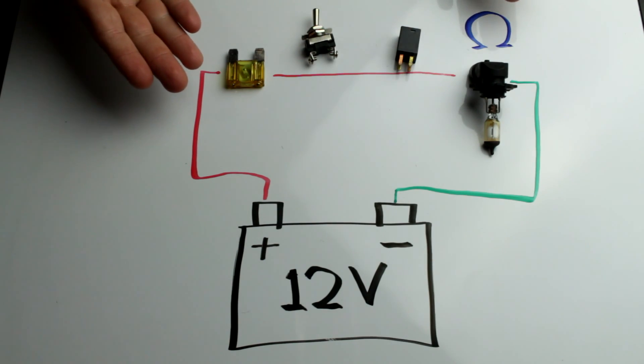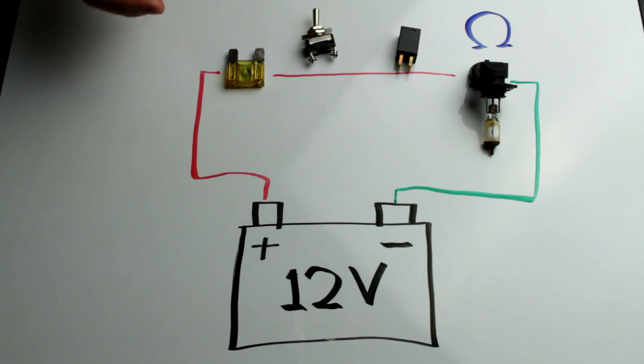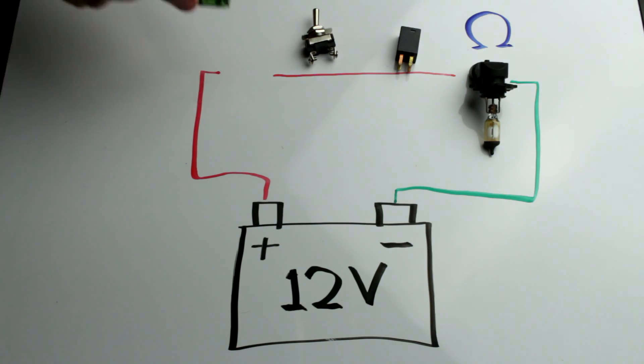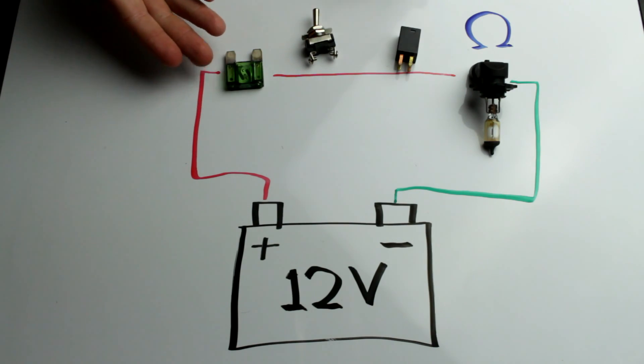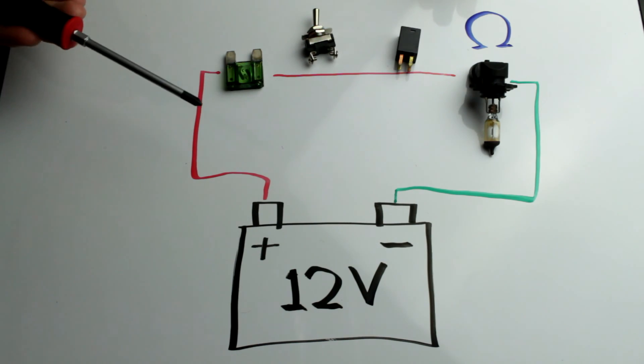If you accidentally started running 24 amps on this circuit, like we were describing earlier, this fuse would blow out. If you were to use a 30 amp fuse instead, something else on this circuit is going to burn up instead. When it comes to replacing parts in a circuit, typically the fuse is both the easiest to get to and the least expensive.